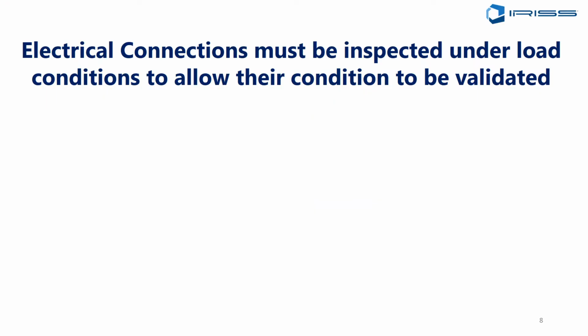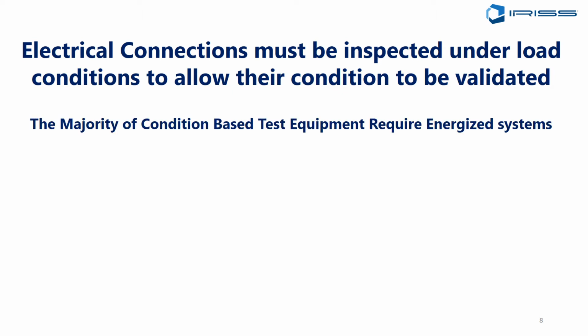So electrical equipment must be inspected under load. If you look at standards like NFPA 70B, for instance, they say that you need a minimum of 40% load. Now, some of our systems are so well designed that we don't run at 40% load. There's so much redundancy, whereas other systems have been stretched so much they might be running 110% over their original design values. So there's lots we've got to look at.